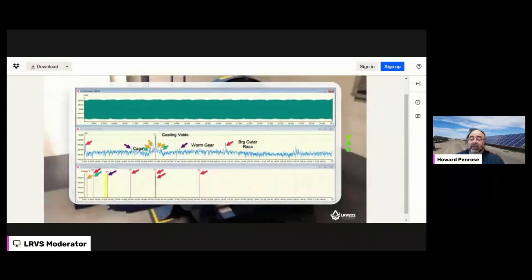And that is literally, once I take that one part in the center, now sometimes I have oscillating loads. What ends up happening is it gets filtered. But in this case, when I take that centerpiece, as you can see, the two gold arrows in the middle, those are actually casting voids in the rotor. Do I worry about casting voids?